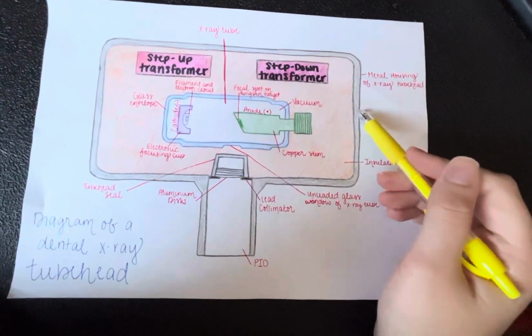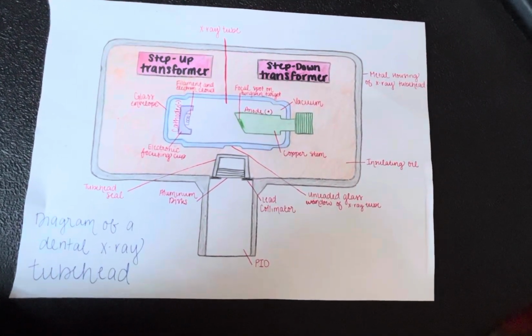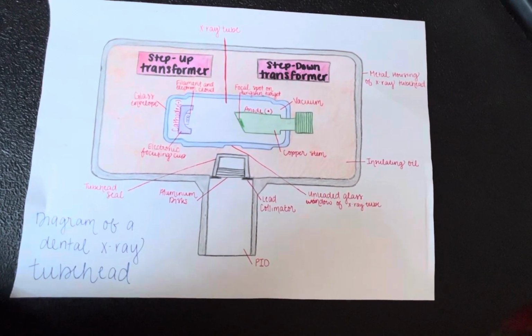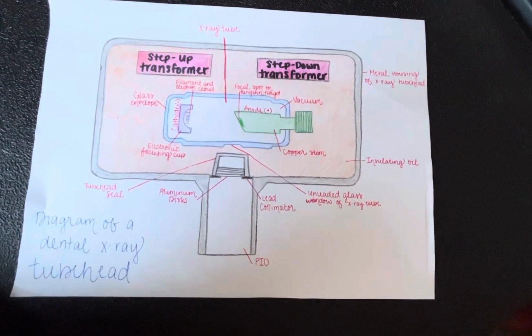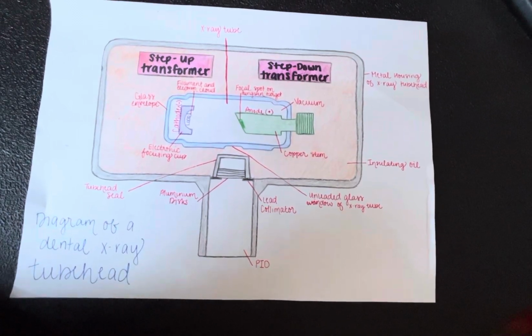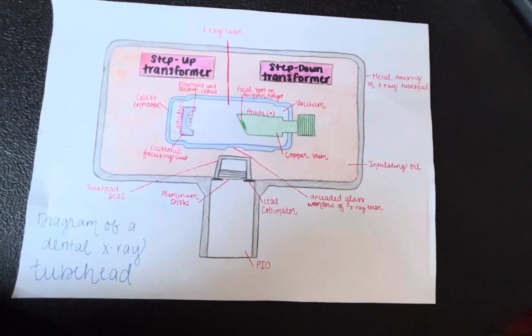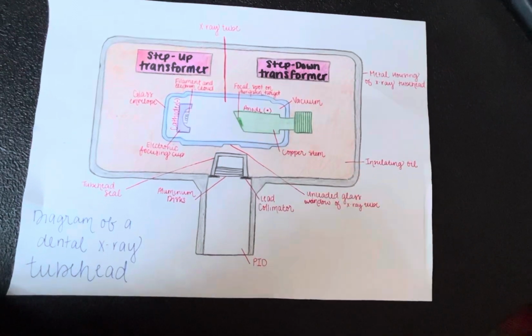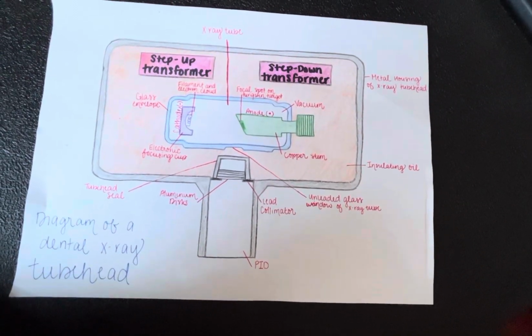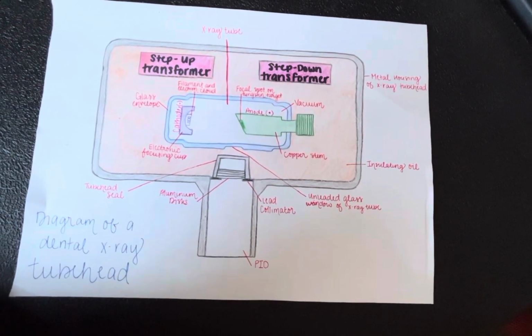First, we have the metal housing, which is also known as the metal body of the tube head that surrounds the X-ray tube and transformers and is filled with oil. It protects the X-ray tube and grounds the high voltage components. The insulating oil prevents overheating by absorbing the heat created by the production of X-rays.